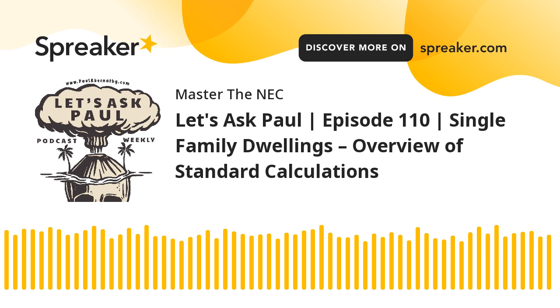Let's say it was a 12 kW electric range, and we know that 220.55 says that I'm just going to go with 8 kW because it's one appliance and it's not over 12. So I can use the demand values in Column C. So it's 8. Don't get lost that it's still a 12. We're allowed to use 8 for this. So I take that 8,000 and multiply that by 0.70, and that's 5,600. That is my neutral contribution, right?